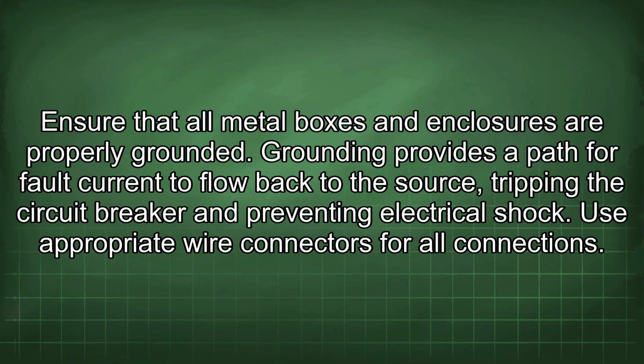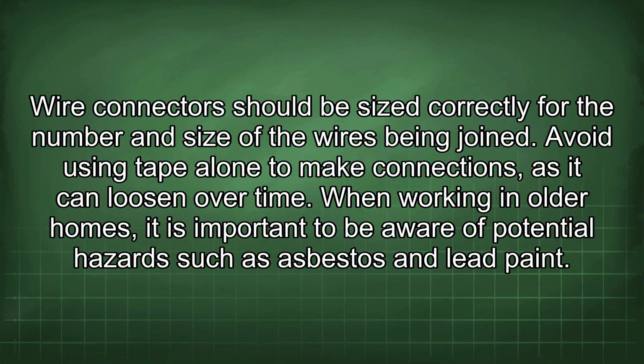Ensure that all metal boxes and enclosures are properly grounded. Grounding provides a path for fault current to flow back to the source, tripping the circuit breaker and preventing electrical shock. Use appropriate wire connectors for all connections. Wire connectors should be sized correctly for the number and size of the wires being joined. Avoid using tape alone to make connections, as it can loosen over time.